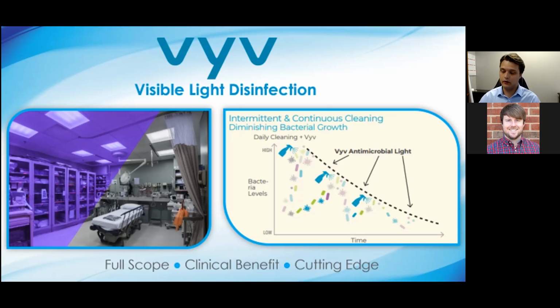One thing to note is it's not an active defense system in that it can't zap bacteria that comes off of a nurse before it gets into that patient. It needs a longer exposure time to kill any of that bacteria. So you still do need that active air defense system keeping bacteria from landing in a wound, but this helps lower the risk of anything being kicked up and added to that level of contamination in the space.